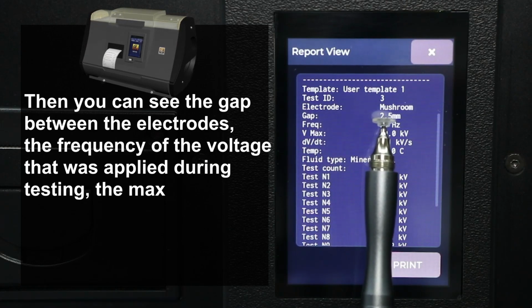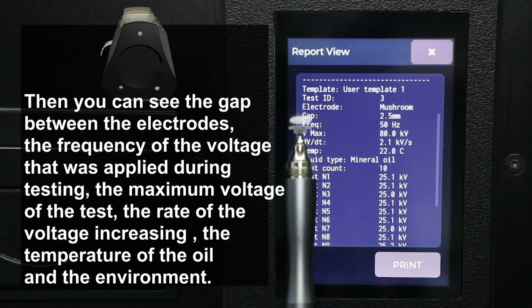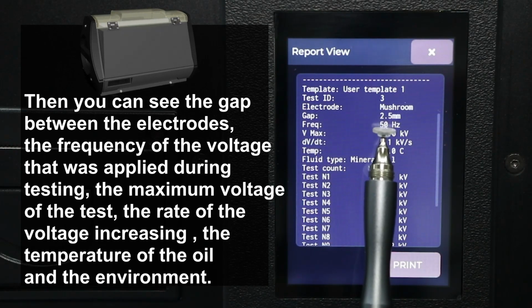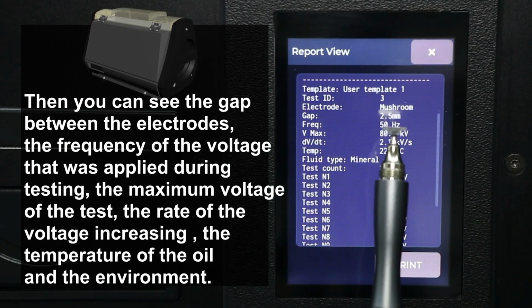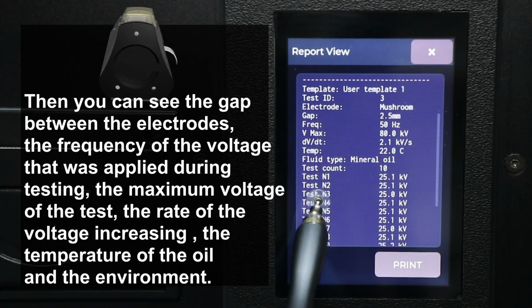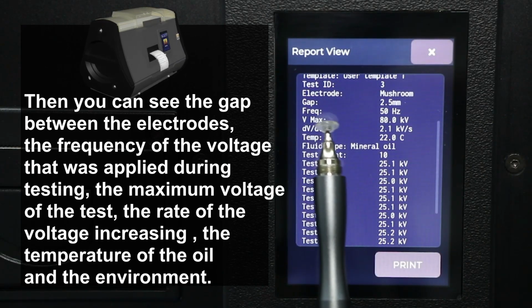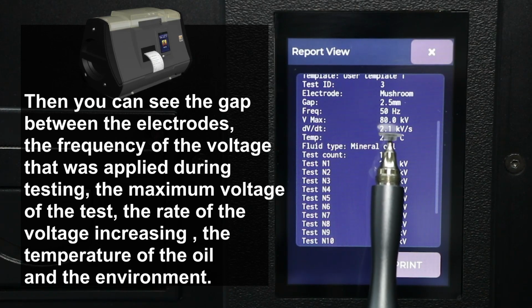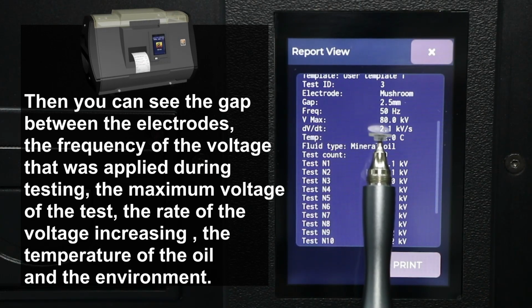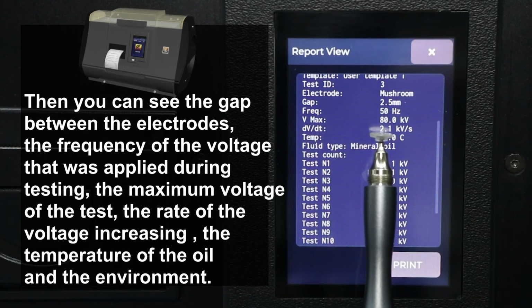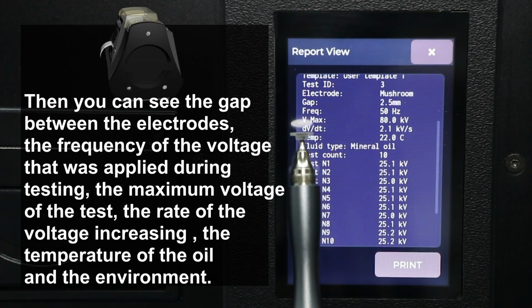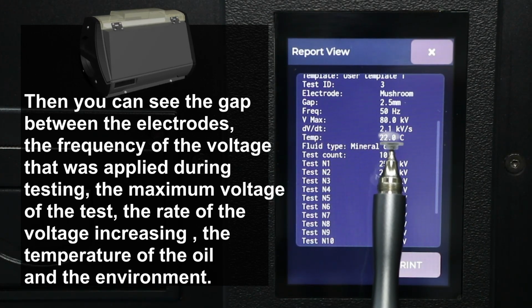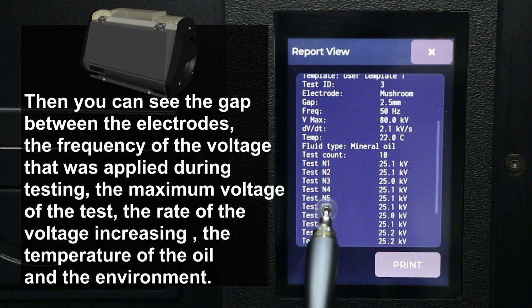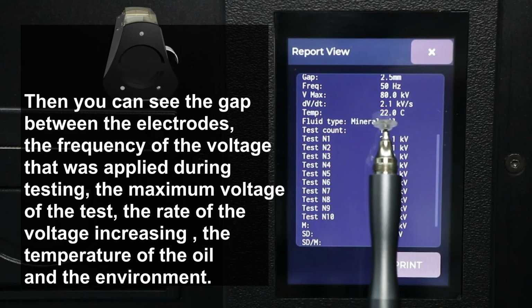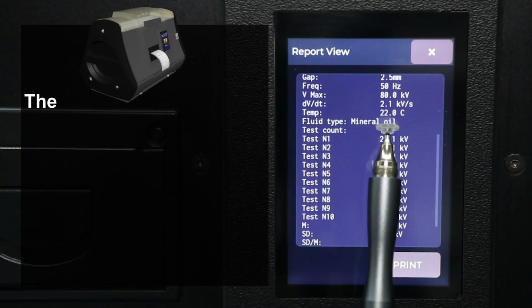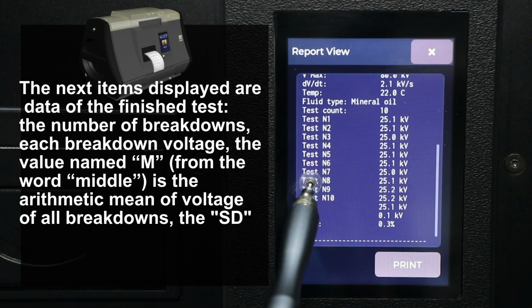Then you can see the gap between the electrodes, the frequency of the voltage that was applied during testing, the maximum voltage of the test, the rate of the voltage increasing, the temperature of the oil and the environment. The next items displayed are data of the finished test.